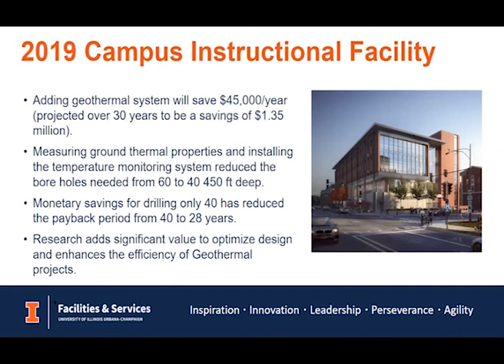Adding a geothermal system to this building will save about $45,000 per year in operation. Projected over 30 years, that's about $1.35 million. Measuring the ground thermal properties through the test well helped us reduce the number of boreholes needed from 60 to 40 at 450 feet deep. The monetary savings from drilling 40 instead of 60 reduced the payback period from 40 to 28 years. So we can see here a live experiment that research adds significant value to optimize design and enhance efficiency of a geothermal project.